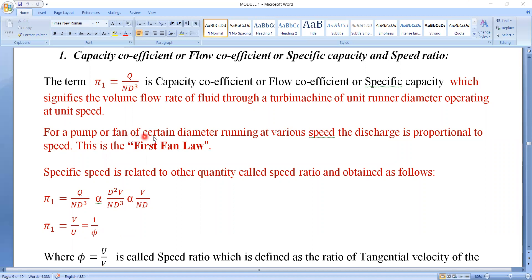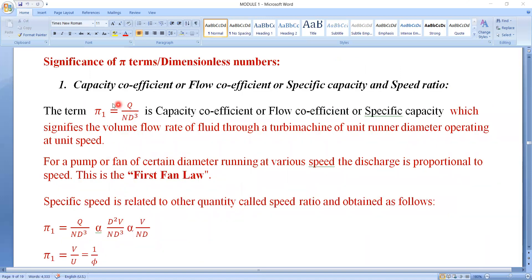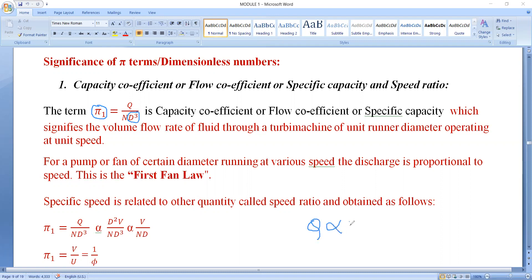For a pump or fan of certain diameter running at various speeds, the discharge is proportional to the speed. If we consider a fan or pump having a certain diameter, then the flow rate Q is directly proportional to N. Since pi 1 is a constant term and diameter is also constant once a turbine is manufactured, the only variables are Q and N. Therefore, Q is directly proportional to N — that is, flow rate is directly proportional to speed of the runner. This itself is nothing but the first fan law.